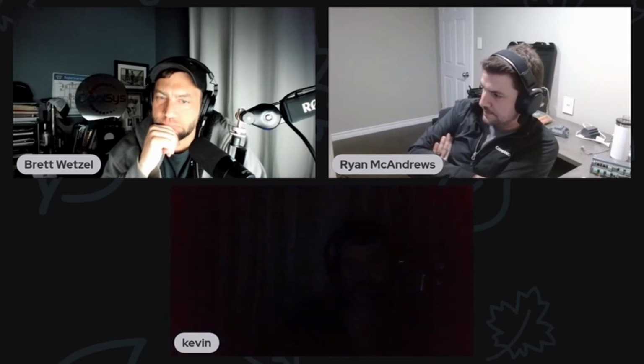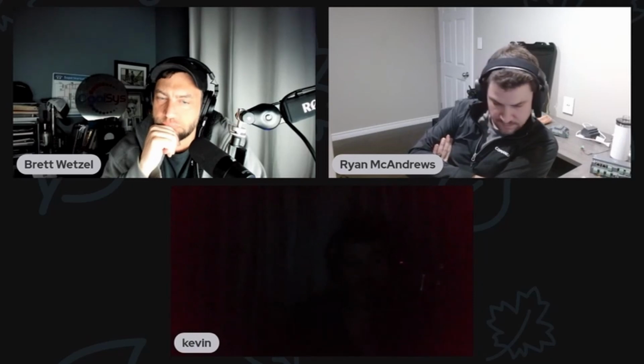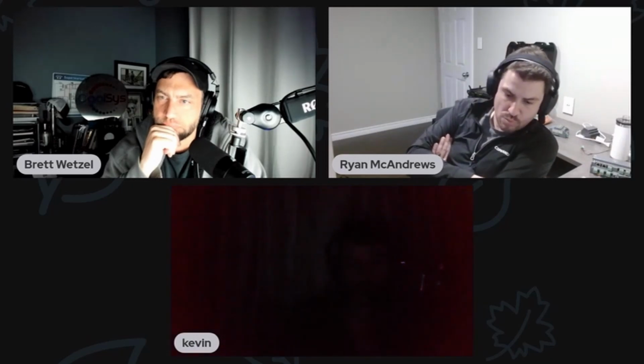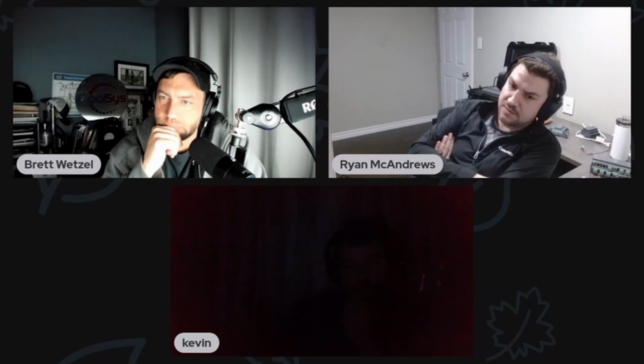What about the crossover between the E2 program and the E3? Does it automatically convert itself? Going from an E2 to an E3, the last time I did it, it converts like 95%. UltraSite, we have a bolt-in where UltraSite can convert 95% of an E2 set point file.